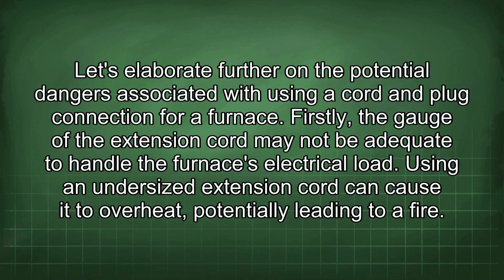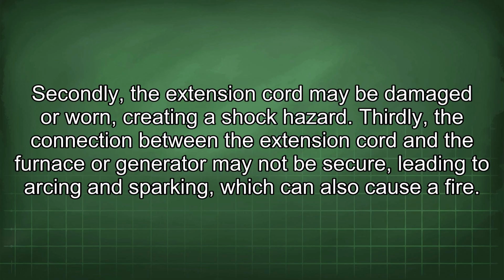Let's elaborate further on the potential dangers associated with using a cord and plug connection for a furnace. Firstly, the gauge of the extension cord may not be adequate to handle the furnace's electrical load. Using an undersized extension cord can cause it to overheat, potentially leading to a fire. Secondly, the extension cord may be damaged or worn, creating a shock hazard. Thirdly, the connection between the extension cord and the furnace or generator may not be secure, leading to arcing and sparking, which can also cause a fire.